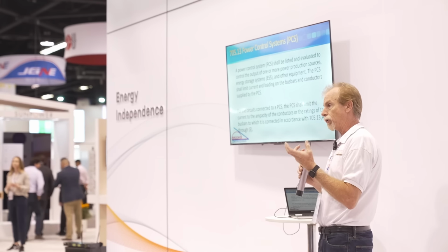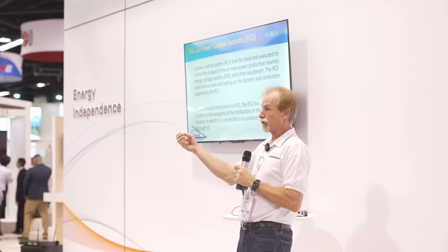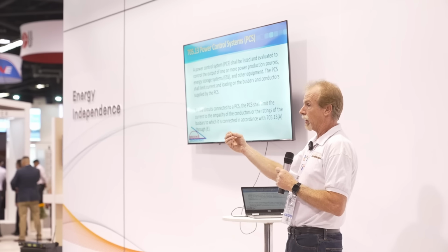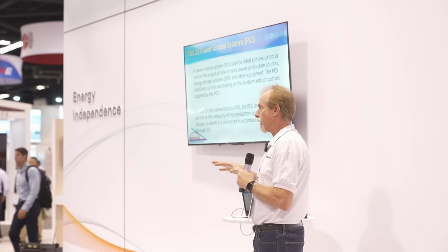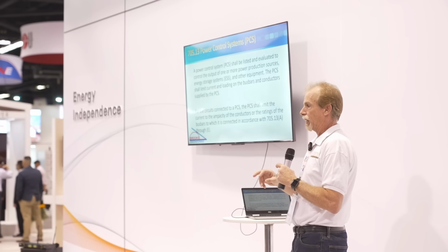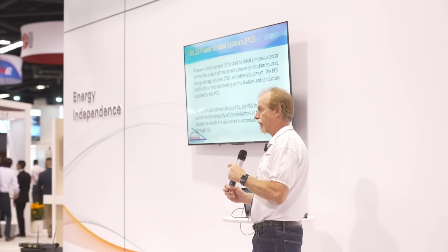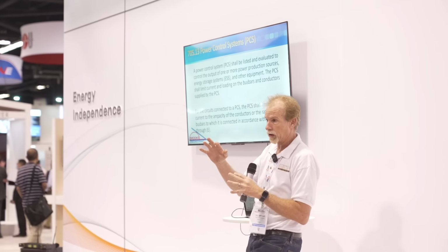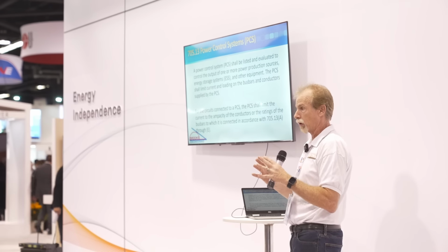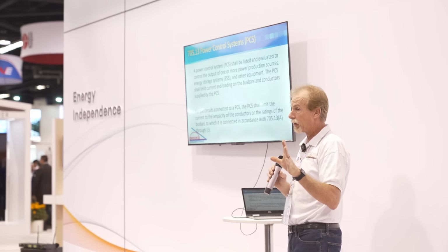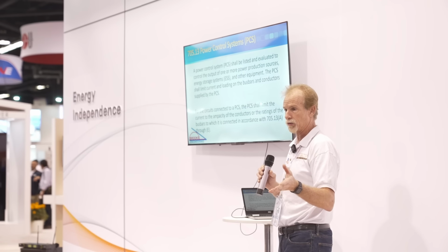And by actively doing that, and if we add the capability of monitoring the service conductors, we can control everything that's going on in this picture, and we don't have to rely on these 120% rule things, which were just kind of throwing things at stuff. And 100% rule, some of the breakers rules, none of those things really matter anymore in panels that are controlled. Now, in the panels that are not controlled, we're going to have to follow those rules.